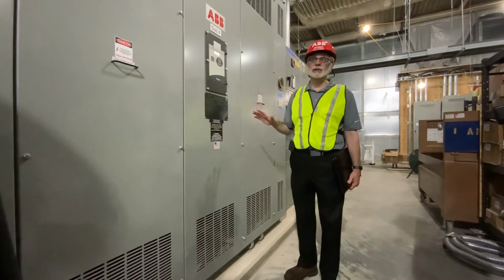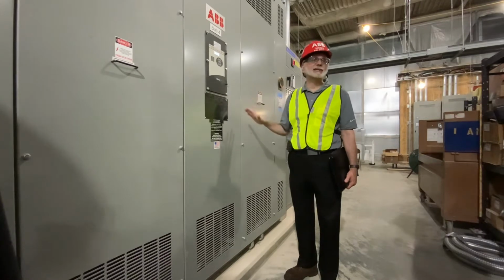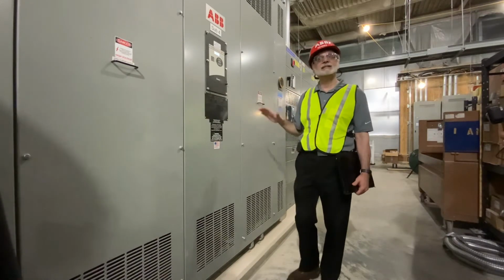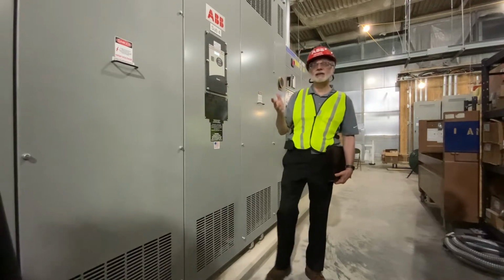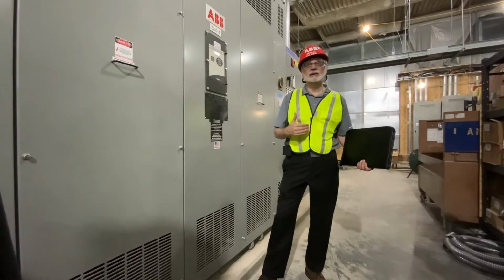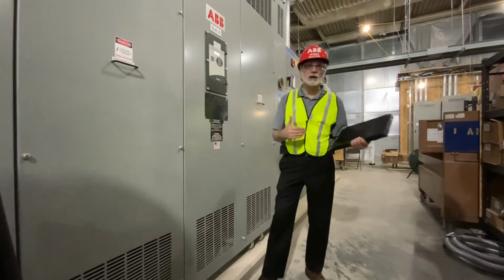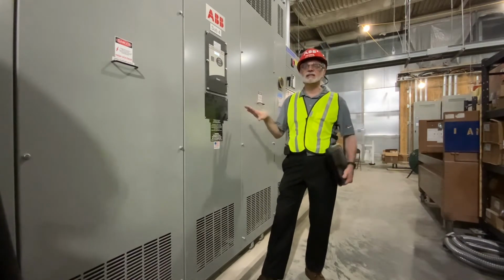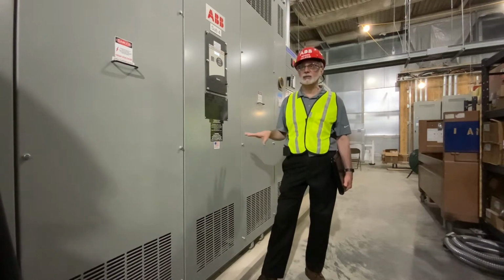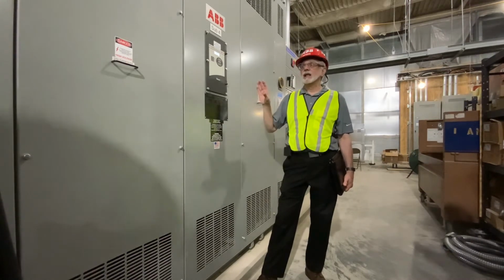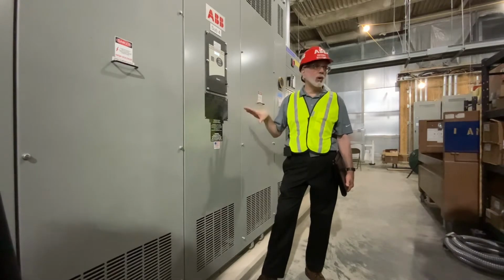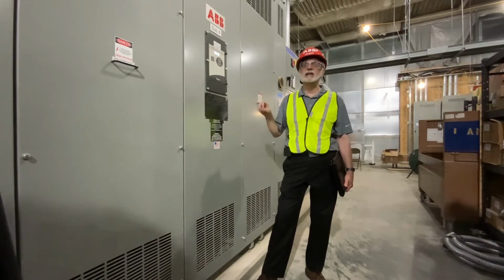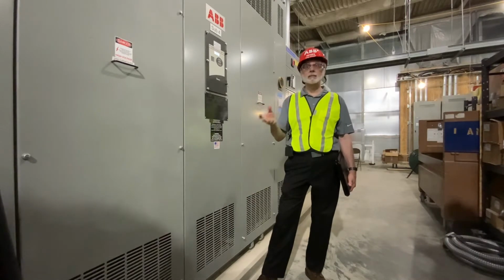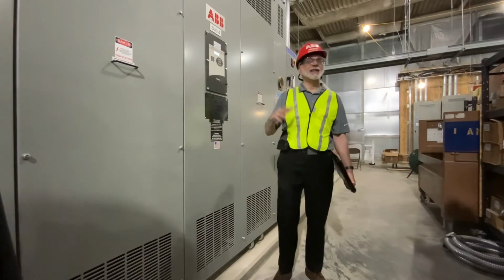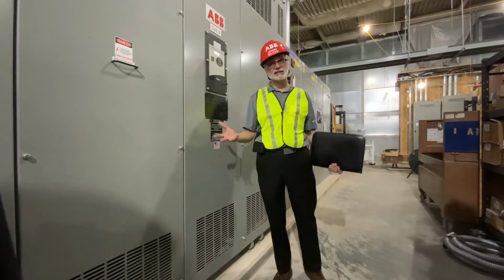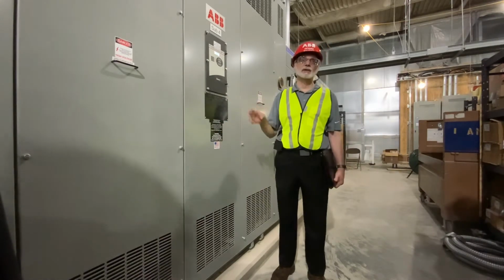Of all the equipment we're going to talk about today, this is the most important one to keep clean. If you're in that situation where you have to go to an every other year maintenance cycle instead of every year, this is the one piece of equipment you want to try to keep on the annual cycle. The reason is, if you get particulate matter on the coils, and that particulate matter is conductive, like cement dust, that's the worst offender. And that's something we all see on job sites, is cement dust. You want to keep that off of the coils.